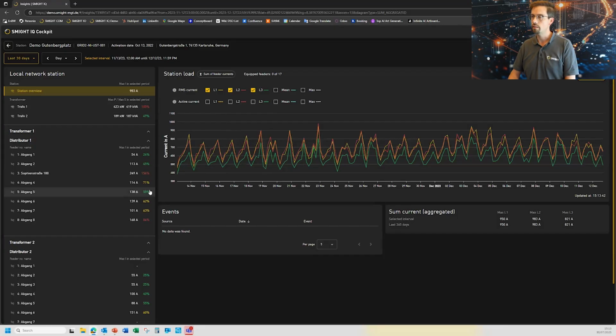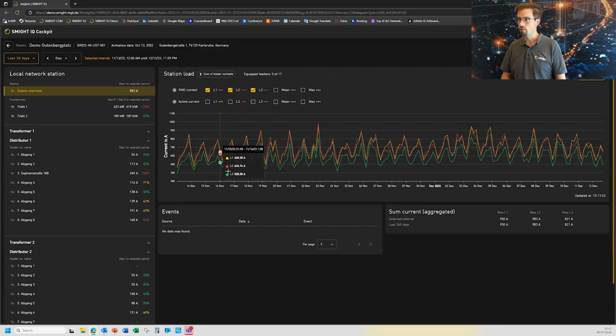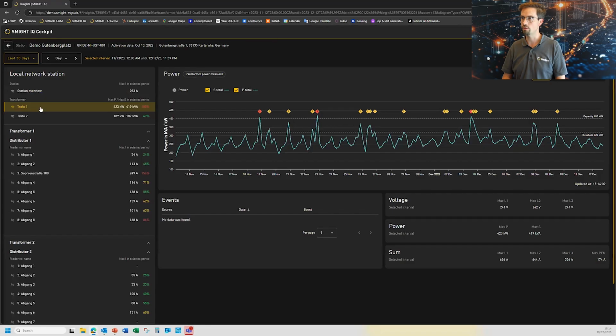In here, as a brief overview of what this system is showing you, this is a substation overview. On the first view, I can see there are 2 transformers and 2 low voltage panels, which I can see down here. Normally, without transformer monitoring, you'd probably be most interested in what's happening at the feeder level, but here we're interested in the transformers, which I see at the top.